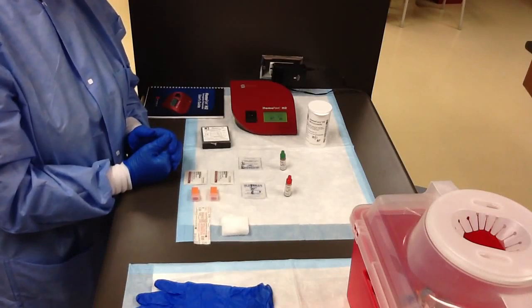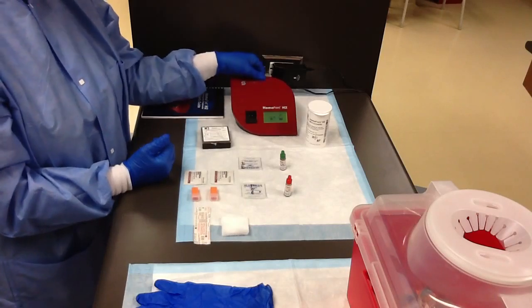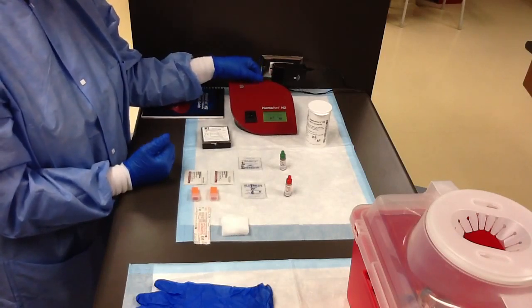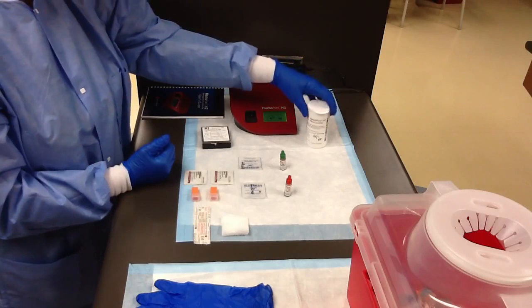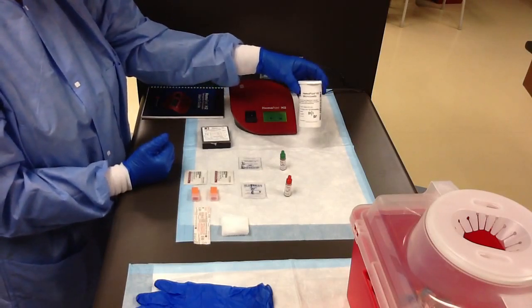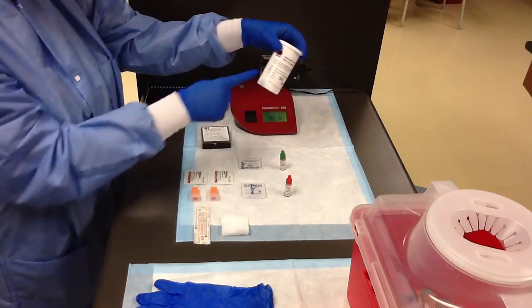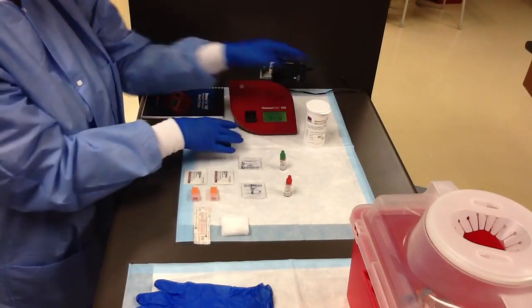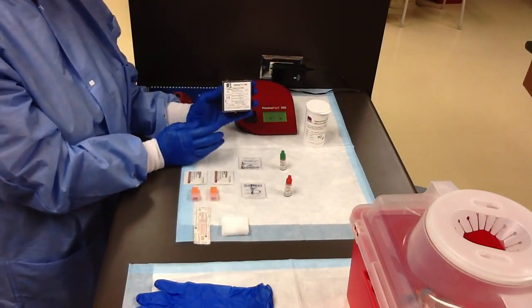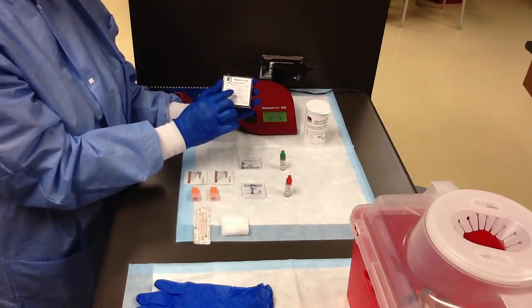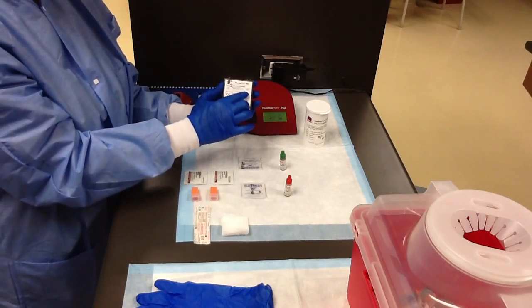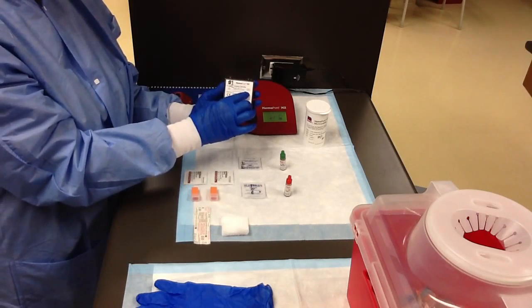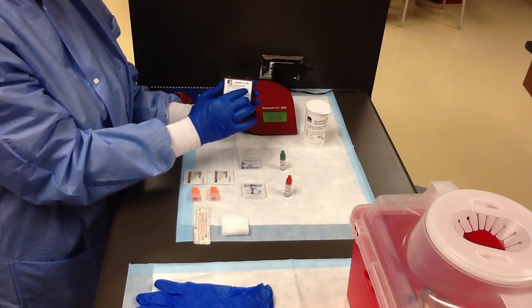Good morning. Today we're going to perform a hemoglobin determination using a Hemopoint H2 photometer. Supplies and equipment needed: Hemopoint H2 microcuvettes. Please note the lot number and expiration date. A hemoglobin control cuvette. Please note that the target value used to calibrate the machine is found on this cuvette.